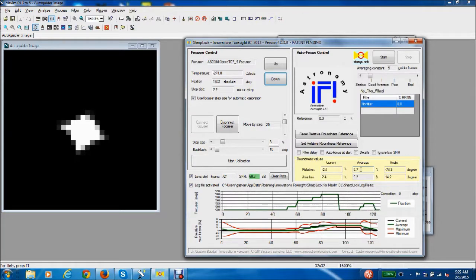You use the relative roundness now because you want to set the reference point for the system. So when this value is stable enough, you can actually set the reference value such that the system will keep that reference value and track it all the time when you are doing the autofocus operation. You see now the values here are more or less stable, and it's time now to set the value as a reference. This reference value will be used by the system to track the focus.